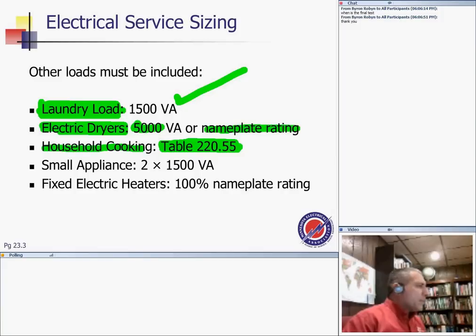And small appliance circuits, guys. Small appliance circuits in the kitchen, it's at least 2 circuits, and each circuit will take 1500 volt amp. And friend, if you ask why 1500, not 2000, it's just that they have to draw the line somewhere. What difference would it make if it was 2000 volt amp versus 1500? They have to draw the line between these circuits. So 1500 volt amp on a 20 amp circuit, I guess that's a good chunk of load.